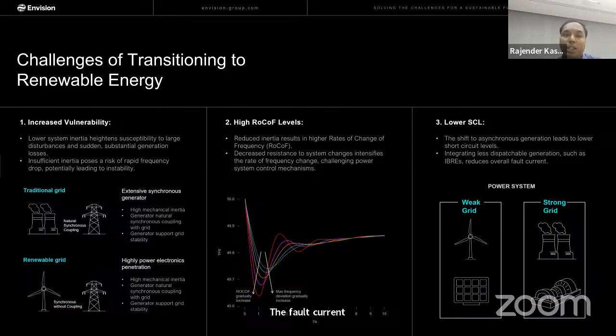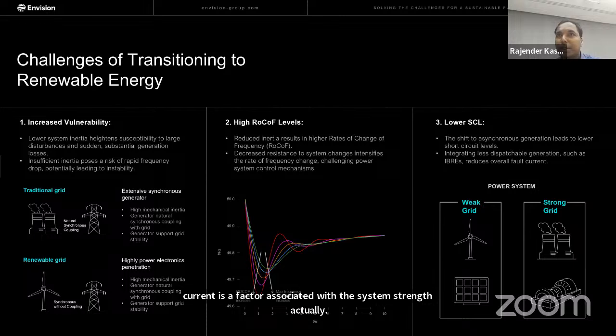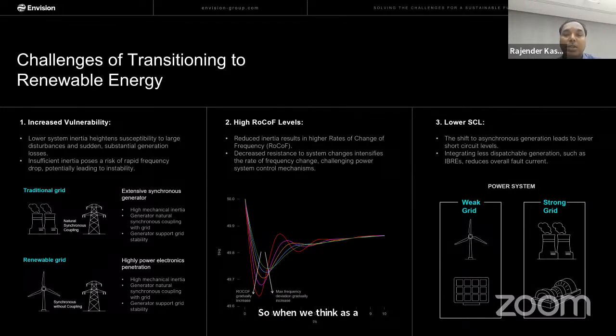When you are going with the lower SCL condition, the fault current is a factor associated with system strength. So when we think of fault current, we think of it in a negative way. But in order for power system protection to work in a sufficient way, all the traditional sources are already contributing the short circuit MVA, the conventional system is already providing it, whereas we are lagging with renewable sources like solar PV inverters.